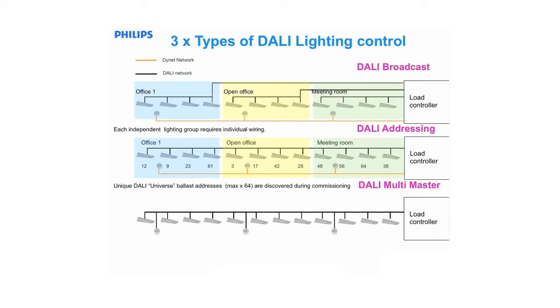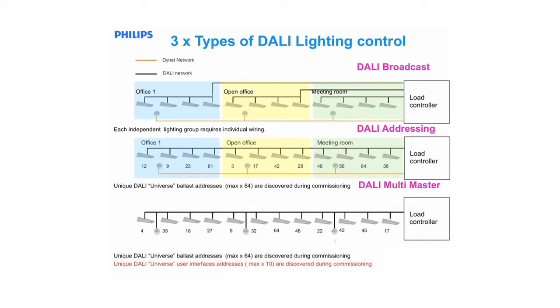Same as before, the individual DALI address information of the ballast needs to be discovered. This is the same enumeration process that is performed in a traditional DALI addressing system. Once the individual ballast addresses have been found, the lighting control system also uses the same process to discover the sensors' unique addresses. The sensor addresses are different from the traditional DALI ballast addresses, and they don't use the same 64 reserved ballast addresses.